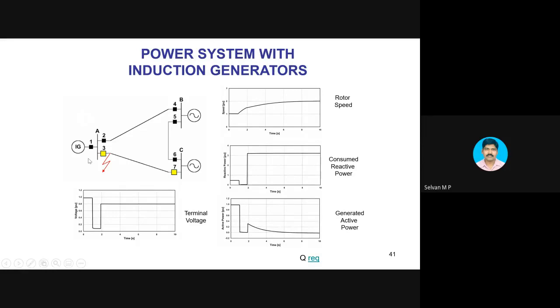So simply the machine will run, there is no active power, and it only draws reactive power from the system. So it is a burden to the grid, and the machine speed is going up enormously. Because of that, mechanical damage will happen. So we have to switch off the machines, no other way. Wind is available, but I'm unable to operate the system. I have to switch off. Again, I have to bring the system back to the normal condition and connect it.